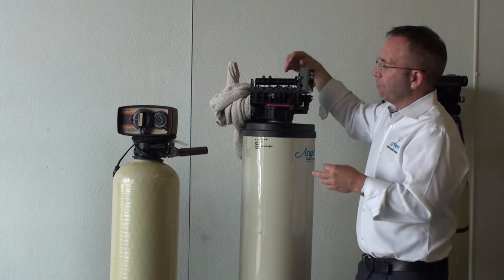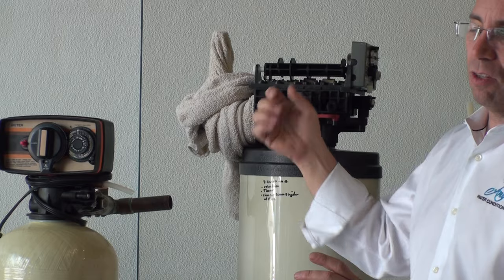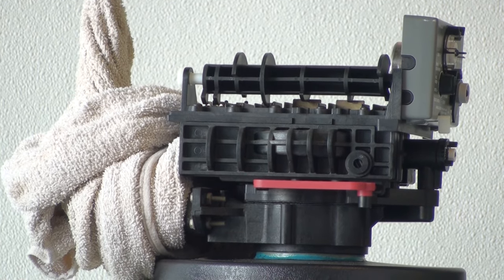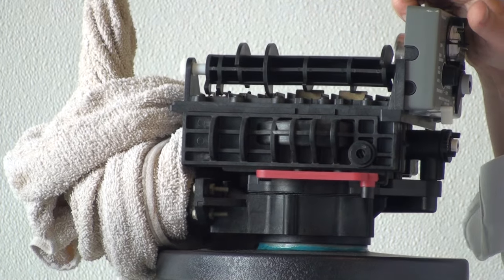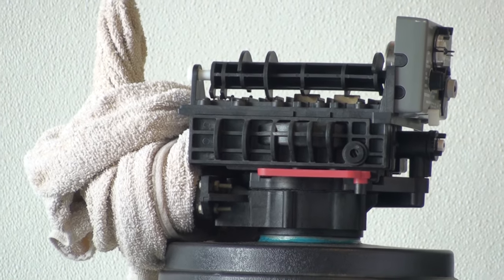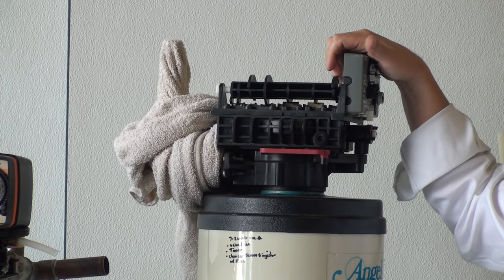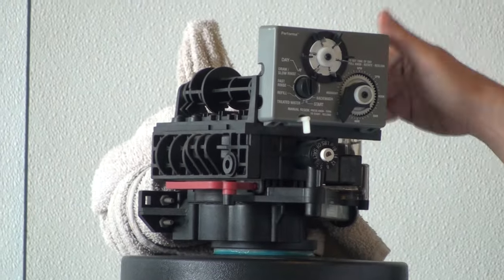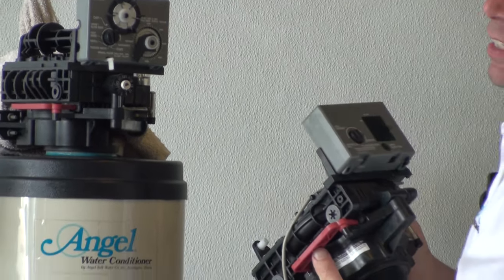As this company evolved itself, it used these ports because they felt that the piston design would get gummed up because you have a piston going back and forth and so they thought the flappers, as they control water going in and out of different ports that do the same thing, draw salt into the unit, backwash itself and rinse itself, they designed this flapper assembly to be easier to operate. One of the complaints about this valve is you actually have to spend a great deal of time to take out the piston, take the seals apart, put a new seal on, and there's what's called spacers, and you have to put the spacers in there, and it's kind of tricky to do. So they felt that they could skin the cat by developing something that's easier to service, so they developed this control valve. It did very, very well. They grew and grew. As they grew, they evolved their product from the 255, or excuse me, the 155 to what's called the 255.